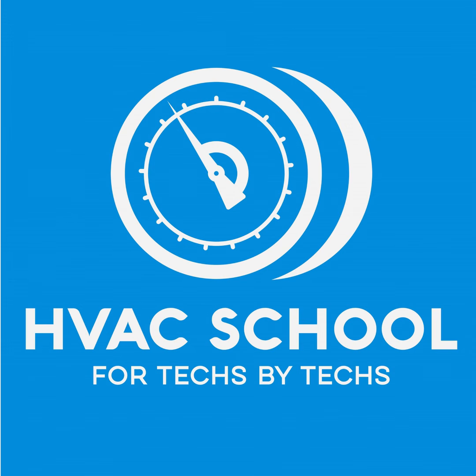Some of the other minor factors, the first one that I kind of scratched down there is defrost reduction. In my climate, when I'm talking about -10, there is such a small amount of moisture in the air at that point, defrost becomes a very, very little factor. Defrost is a bigger issue if I'm sizing for winter conditions of, let's say, 30 degrees, 25 degrees, because I've got more grains of moisture in the air, which is going to cause me to actually frost up at a higher rate. And I'm going to need to go through more defrost cycles, causing me to take a bigger hit on my nominal capacity. So I call that one a minor factor. And it's minor because it is in our climate. I typically tell guys, don't worry about that. And again, that's all factored into the software when you're picking design conditions.